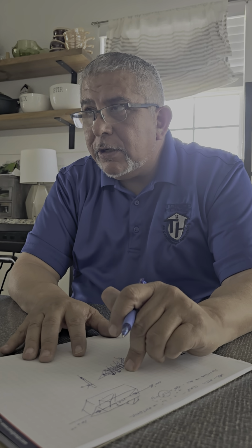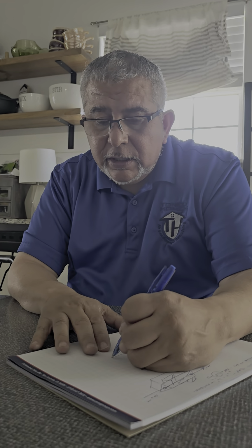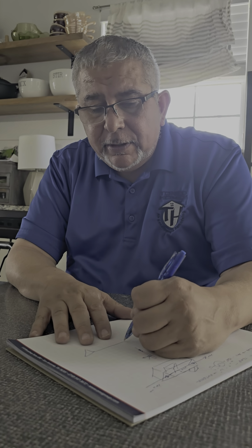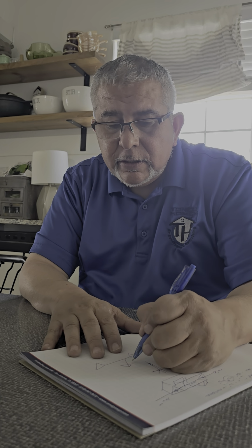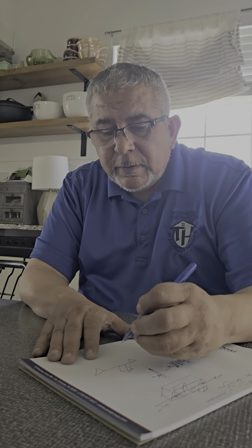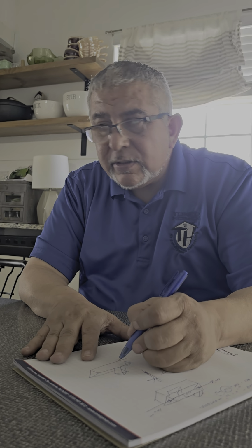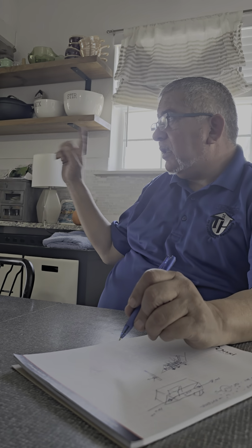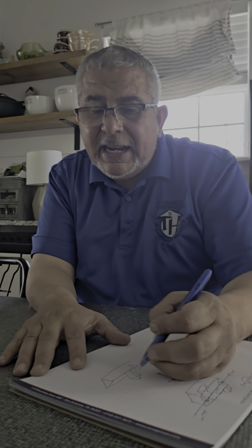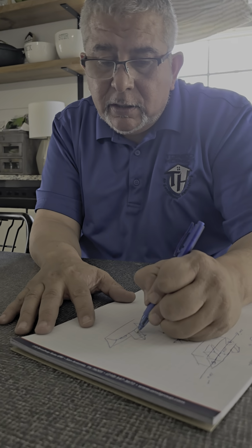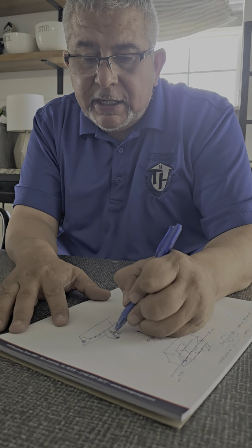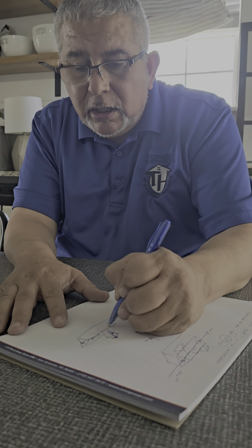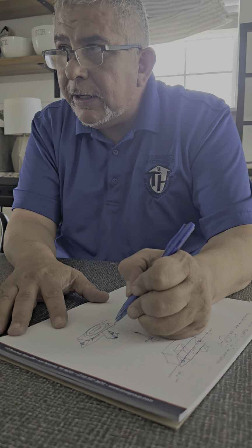Okay, this is what's happening in your house. In your house, you have a gable like this. You have another gable like this. It goes like that, and I think that's it. So you have that, but somebody put a little bitty ridge vent here, a little bitty ridge vent here. You have a gable vent here. You have a gable vent here, and you have no soffit vents. So your air is literally just coming like this and like that. All of this, the air's not moving.